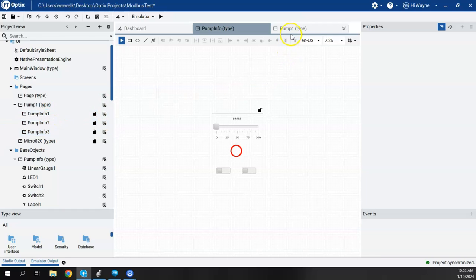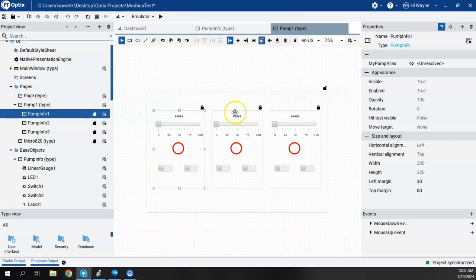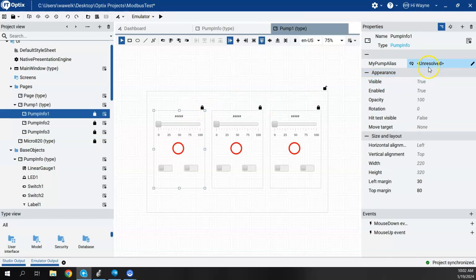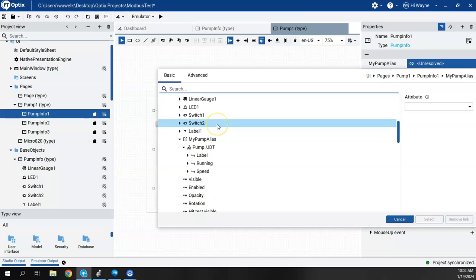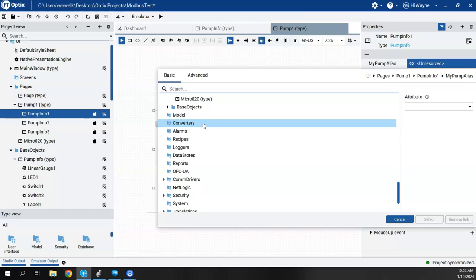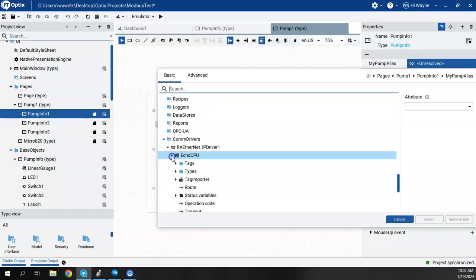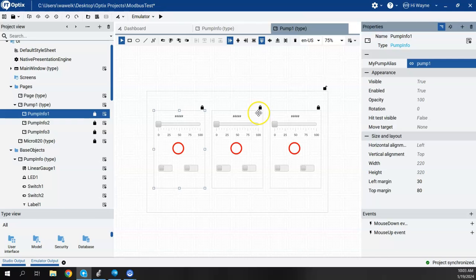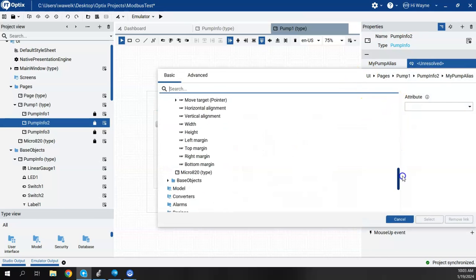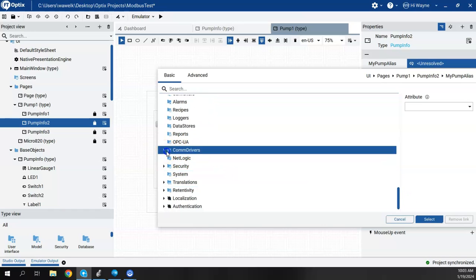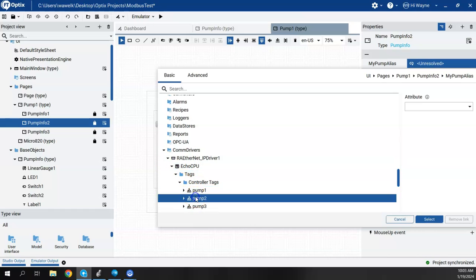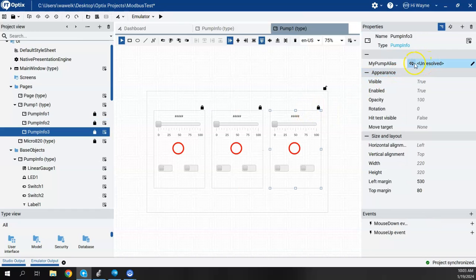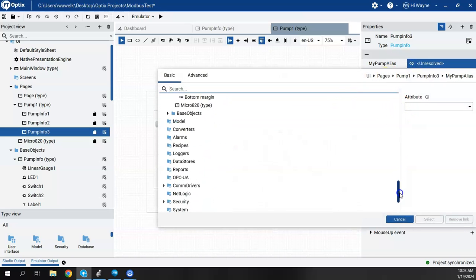Now, coming back to our Pump 1 screen, so here's where I had the three instances, Pump 1, Pump 2, and Pump 3. So since I deleted the model there, now this shows as unresolved. So for My Pump Alias, I'm going to just bring this down to my controller, Comm Drivers once again, and choose Pump 1. For Pump 2, we'll do the same thing. Go down here to Comm Drivers, tags, controller tags, Pump 2. And lastly, for Pump 3 instance, we will do the same thing.